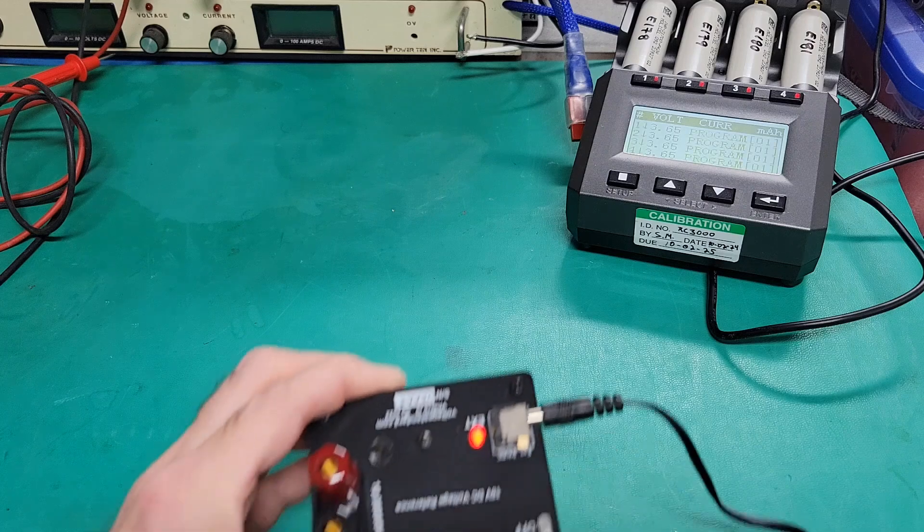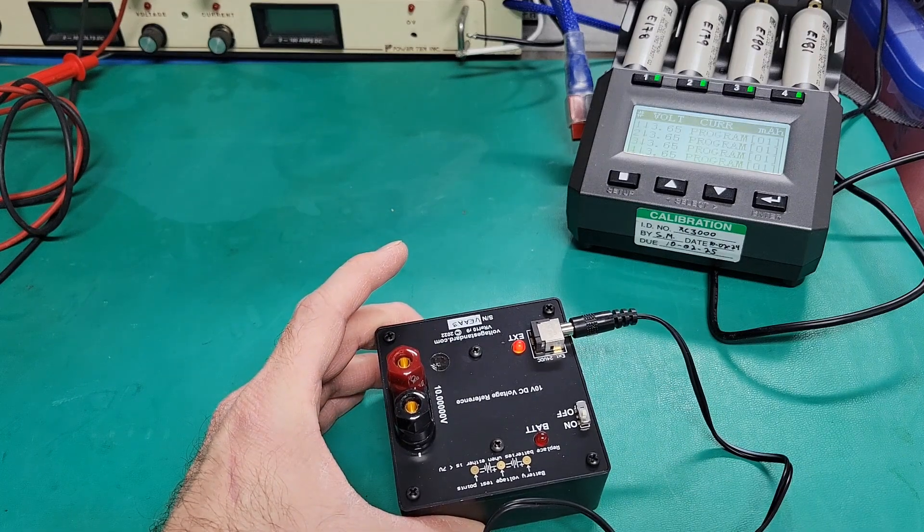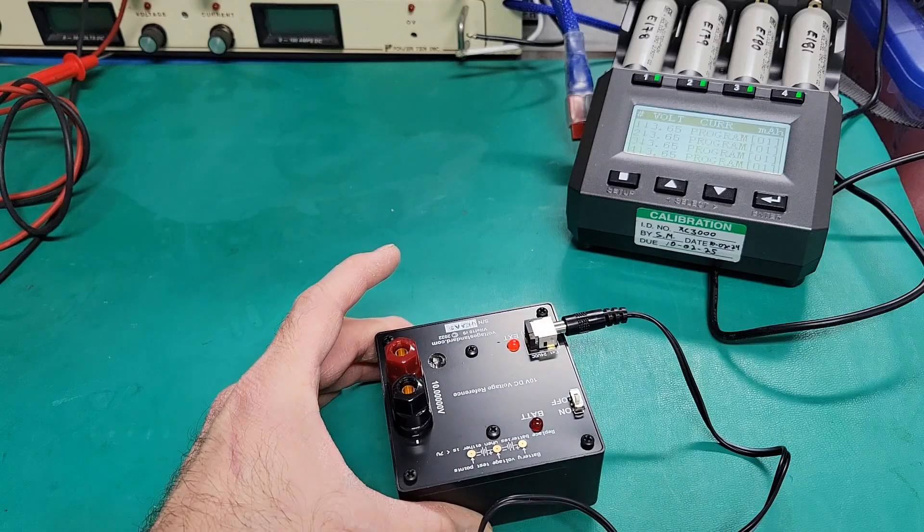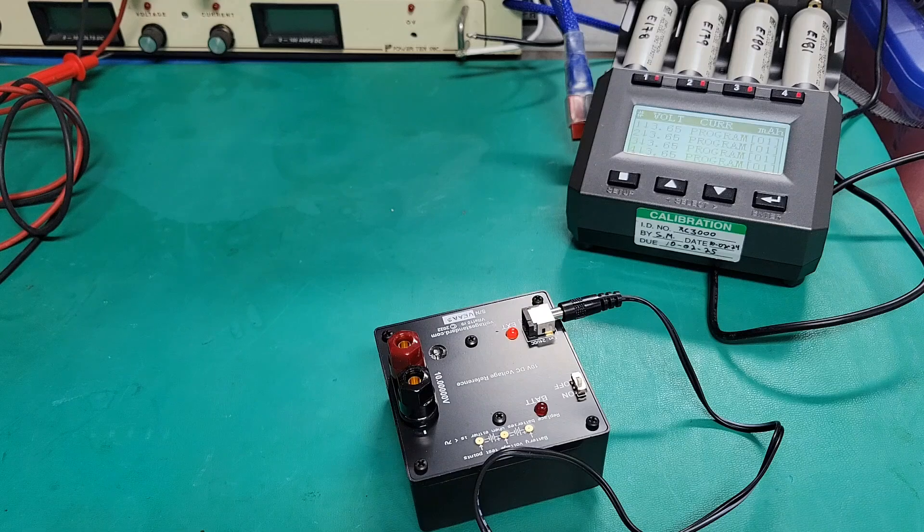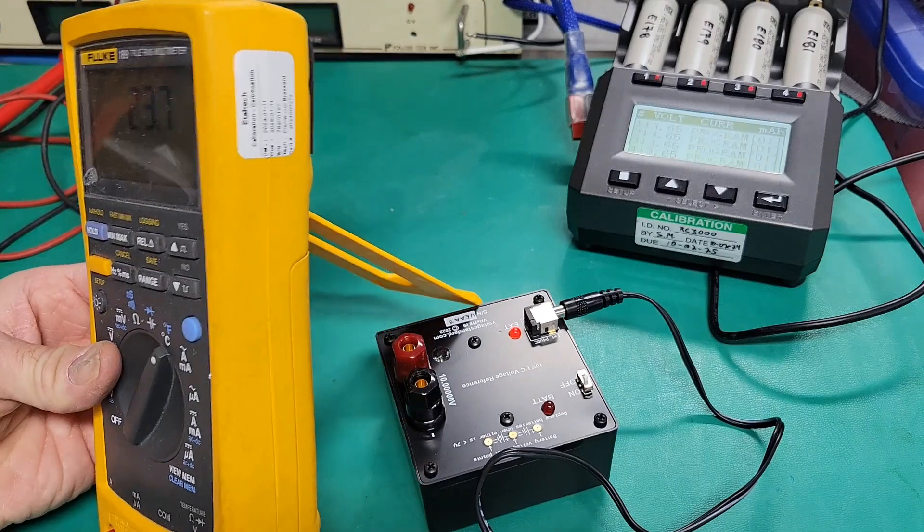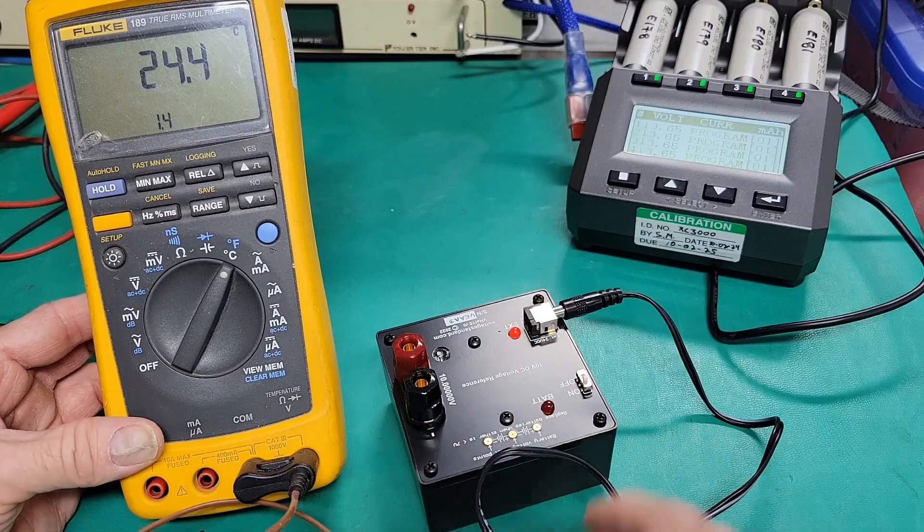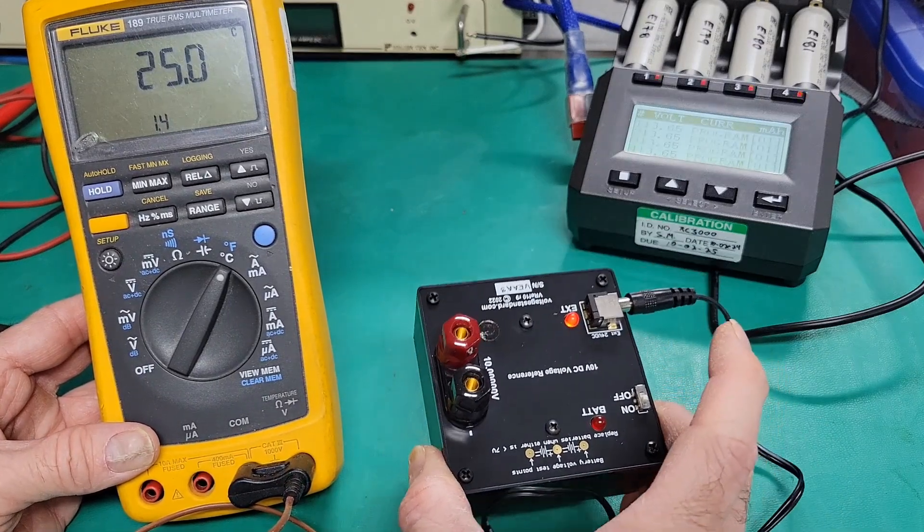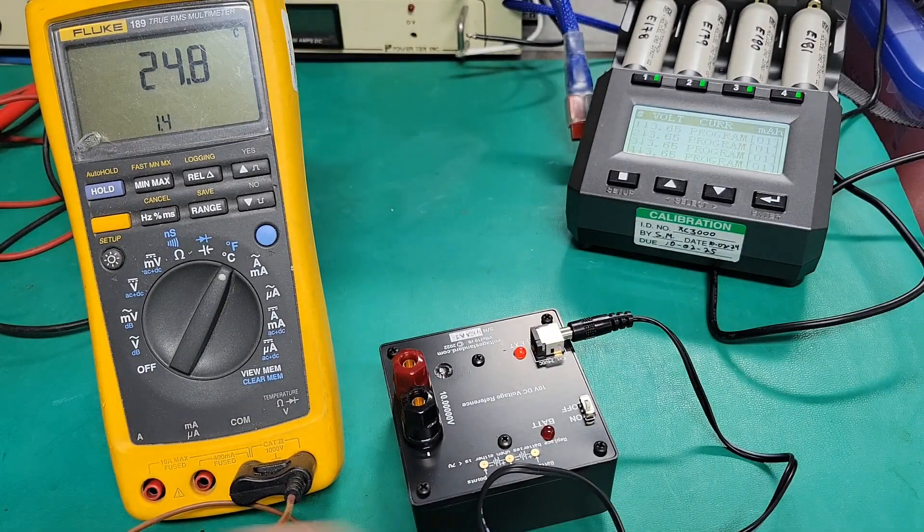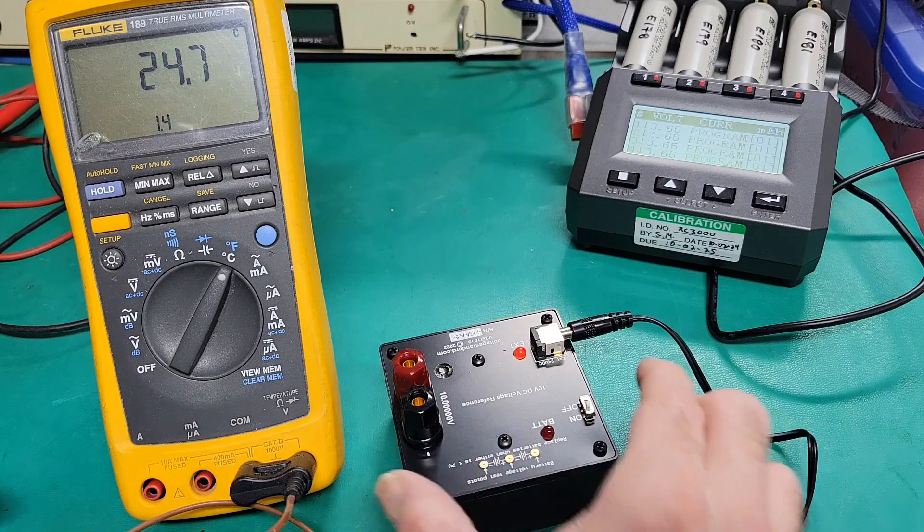So first of all, we will use this voltage reference to measure if my Agilent precise voltmeter is accurate. And to make sure that this one is in the right range of temperature, I will use also this calibrated multimeter with the temperature probe to make sure that the temperature at which I'm operating this voltage reference is right. I have the calibration paper here with the calibration curve and the compensation curve.